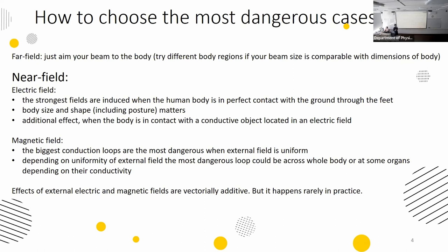For magnetic fields: magnetic fields don't harm you directly by themselves, but they produce induced electric fields in you by Faraday's law. The bigger the conduction loop through which current flows, the bigger the internal induced electric fields you get. Depending on the uniformity of your external magnetic field, the most dangerous loop could be across the whole body volume. In cases when the external field is not uniform, the biggest loop could be within some specific organs. The biggest induced fields also depend on the conductivity of the tissues, and these effects are vectorially additive.